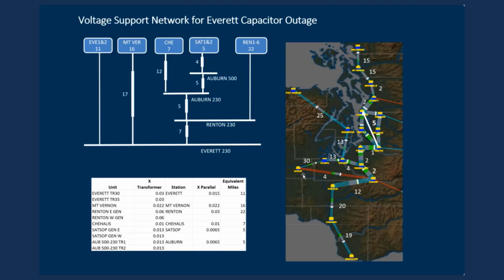And so we notice that Satsop also feeds into the Auburn station. So when we have a station which is fed by multiple supporting generators, we have to model that explicitly in our network. For the Satsop unit, we go through 4 miles, which is the equivalent of the 500 kV, and then we have to go through 5 miles to go from the 500 kV bus to the 230 kV bus. That 5 miles is those two 500 to 230 kV transformers working in parallel. And then from the Auburn 230, we come on up to Renton.